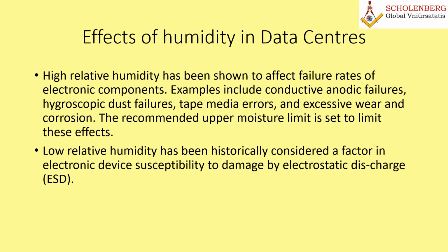The recommended upper limit is already mentioned in the previous tables. It depends again on the class, A1, A2, A3, A4, then B and C. It is clearly mentioned what the recommended relative humidities should be. Now let's go to lower relative humidity. What are the disadvantages? Please listen very carefully. Low relative humidity has been historically considered a factor in electronic device susceptibility to damage by electrostatic discharge, that is static discharge or ESD. However, the new ASHRAE research suggests that susceptibility to low relative humidity is of far less concern than once was thought. That means low relative humidity is not a concern for the data center.